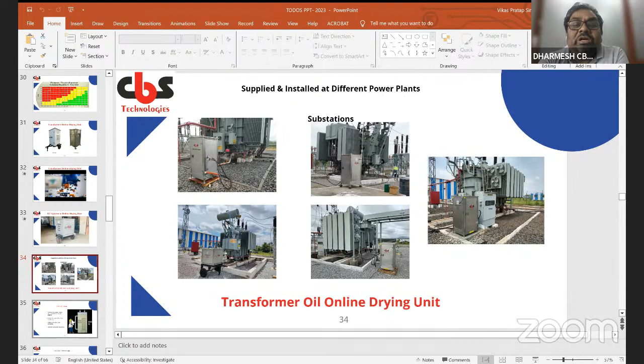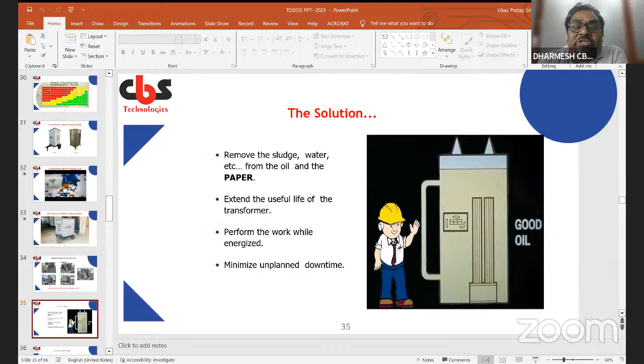This is how the system works. It removes the sludge, water, etc. from the oil and paper. It extends the useful life of the transformer. The basic idea of this system is that it works while the transformer is in energized condition, and the unplanned downtime will be much less if you put this system in.